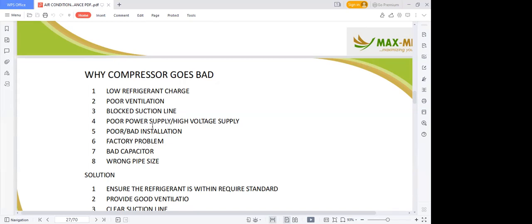Then a bad capacitor. Sometimes when a system goes down, it is the capacitor within the system that has gone bad. So you need to buy a capacitance measuring device to be able to measure the capacitor. Say a capacitor is rated 50 microfarad, and you notice that it is not working properly. You measure it and discover that it is giving a reading of 10 microfarad. Know that that capacitor is gone. So you go to the market, buy the same capacitor, bring it back and install it, and your unit will be up and running.